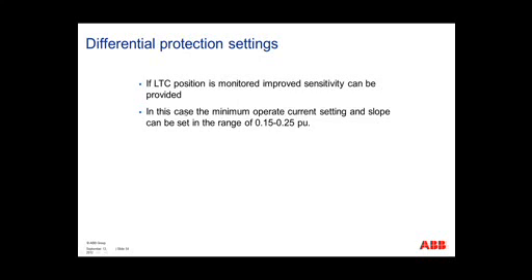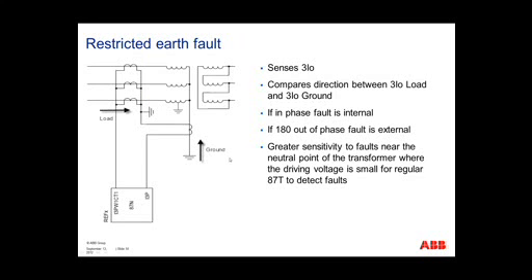So, I mentioned before, if the load tap changer position is monitored, you can actually increase the sensitivity of your pickup setting. If you can monitor your load tap changer and what position it's at, you can set your current and slope setting at about 0.15 to 0.25 per unit.